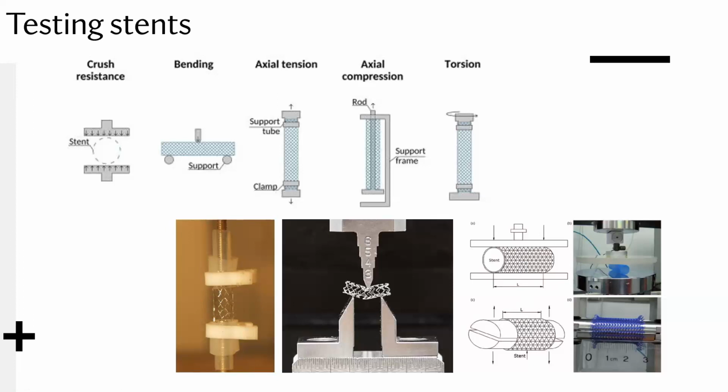When does it burst? Because then you have compression of the blood vessel, you have the inflation of the blood vessel whenever you're looking at the high pressure peaks, and depending on where this is deployed, these could each have increased levels of importance. And here you're actually stretching it also using this specially designed fixture. It's notable that even for the stretching, as you can see, you cannot do it with a simple clamping feature because it's a very delicate structure.